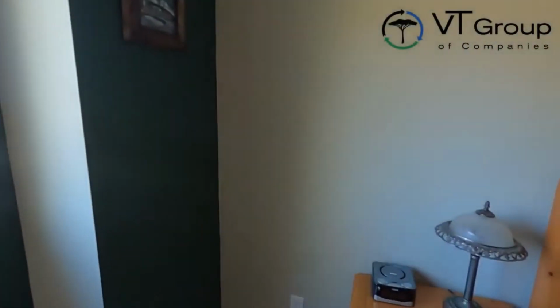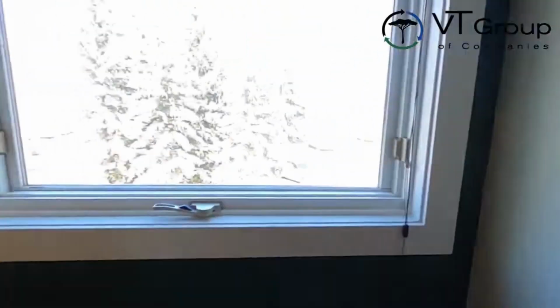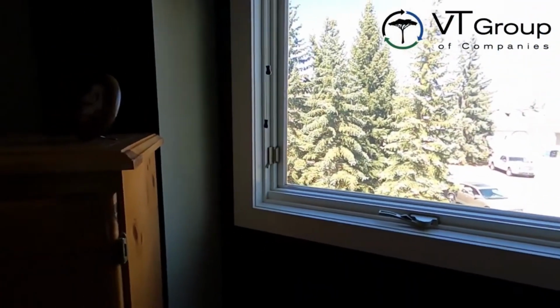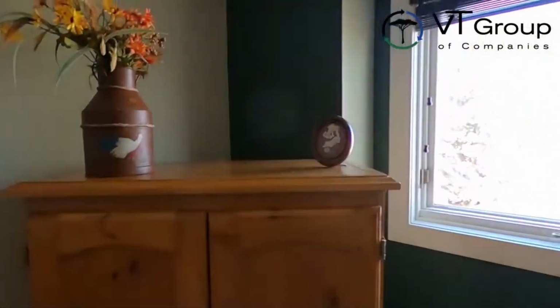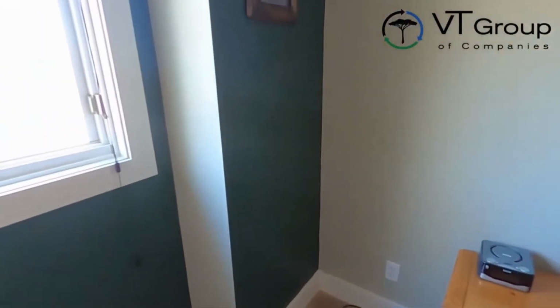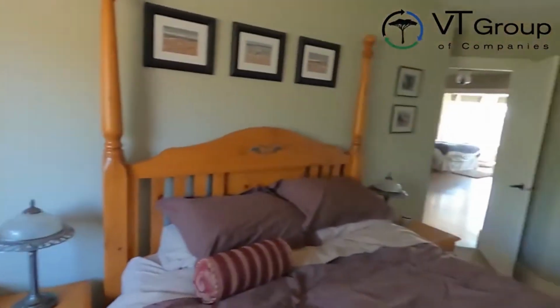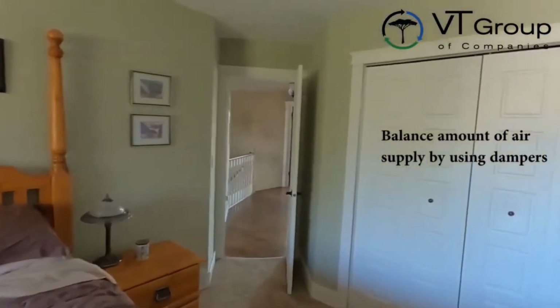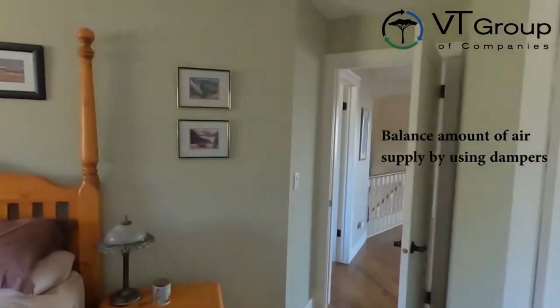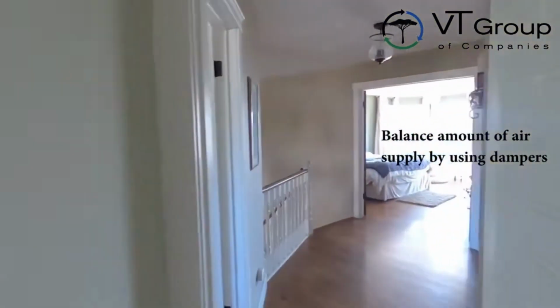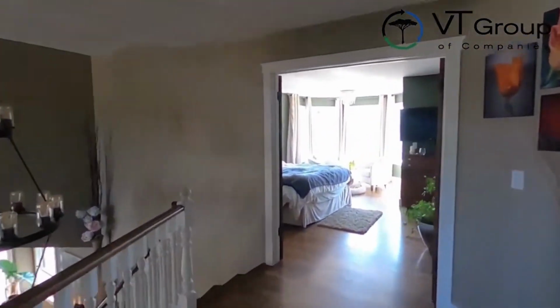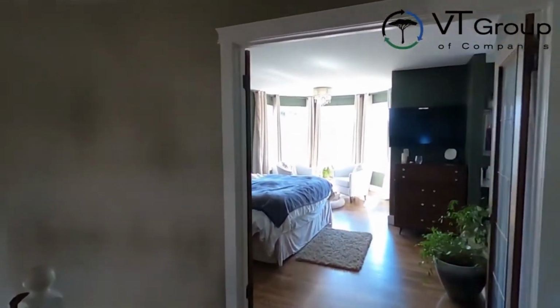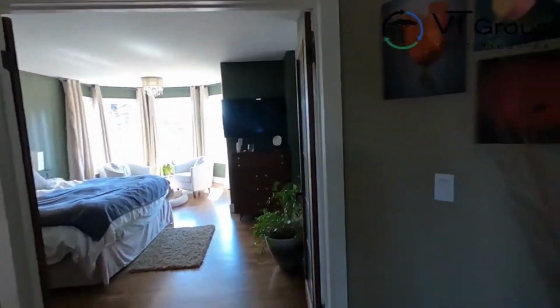But the other thing that's happening in this room, we've also got an exposed wall. I've got an exposed floor, which means it's a colder floor, colder walls, and a ceiling. So this may need more air than other areas of the home. So that's that air balancing, right? So you can control the amount of air using the dampers in the floor registers, kick plates, and areas that are sort of further away, but exposed floors will need more air.